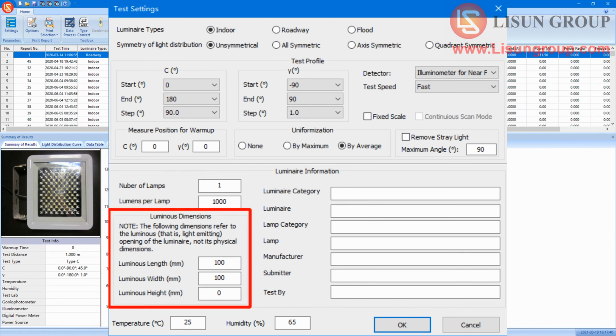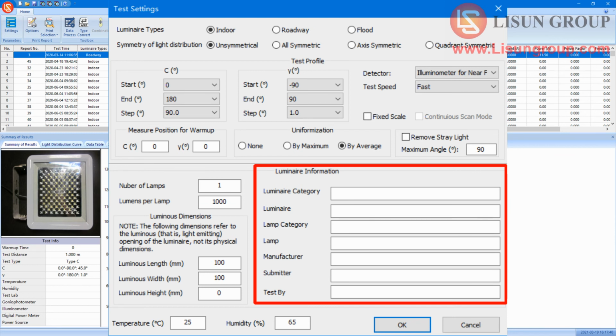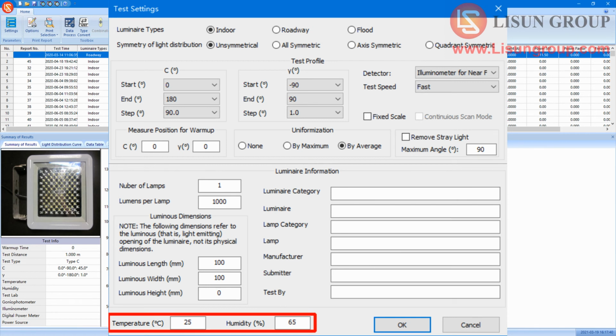Input the luminous dimensions. Input the information of the sample. Input the temperature and the humidity of the darkroom. Click OK to enter the preheating interface. If you did not check warm-up, it will enter the testing interface directly.